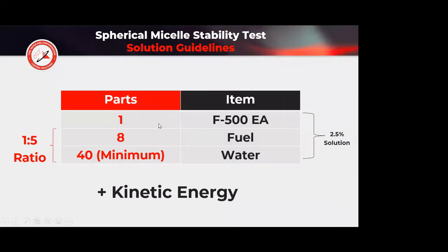Interesting ratios here: the ratio of 1 part of F500 to 40 parts water is 2.5%. That's why we use the F500 at 3% for Class B fires. It's giving us a 20% factor of safety. So we're taking 2.5% and we're applying at 3. Most of your equipment, your proportioning equipment, is all geared for 3%.